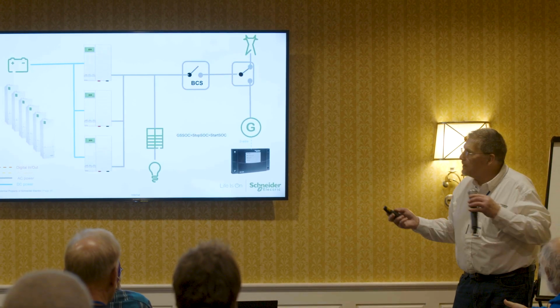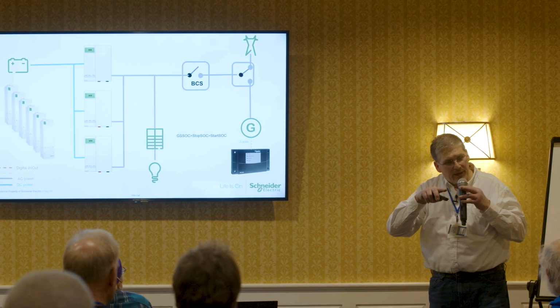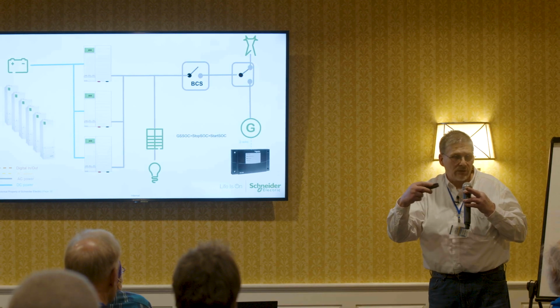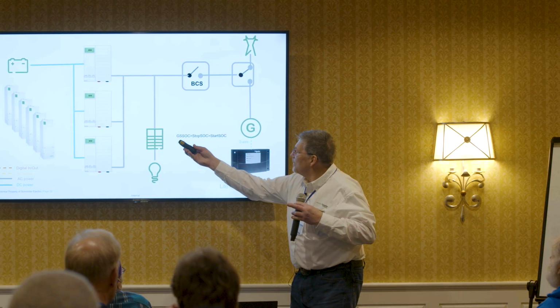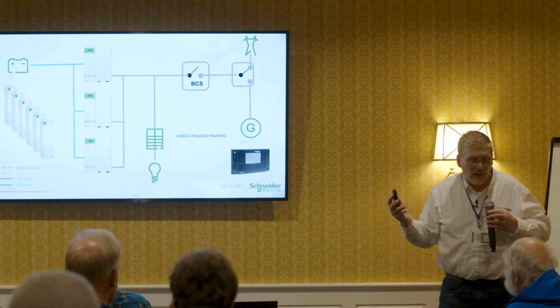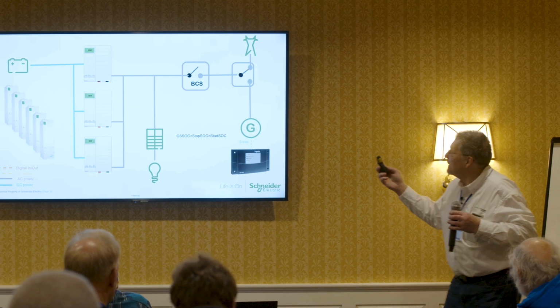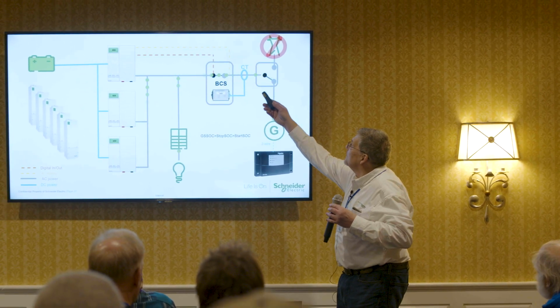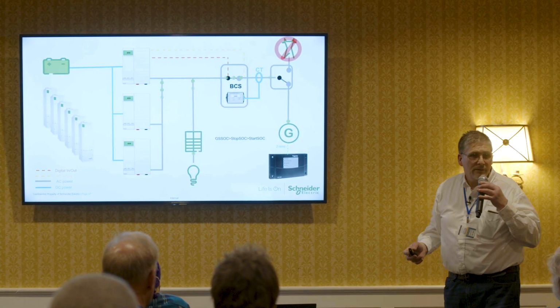Right, no, there's not, because we're using a single point of connection, which is AC1, we have to be careful in our programming to make sure that we're not selling back to the generator. That's why I said we have to make sure that our grid support SOC is higher than the stop SOC, so we're not allowing the generator to be exposed to any sell power. But again, if you're using the watt node meter with the CT, it's not going to sell anyway, whether we're connected to the grid or a generator, right?